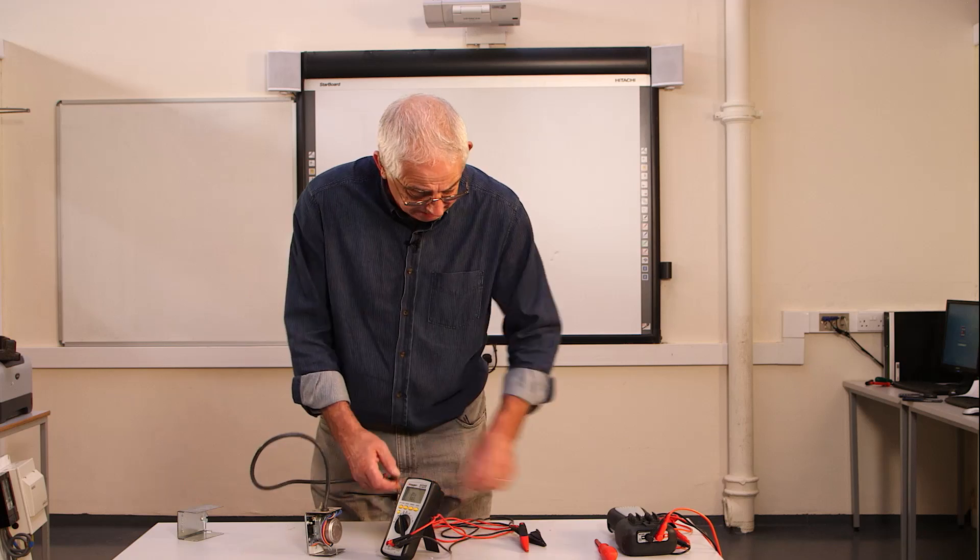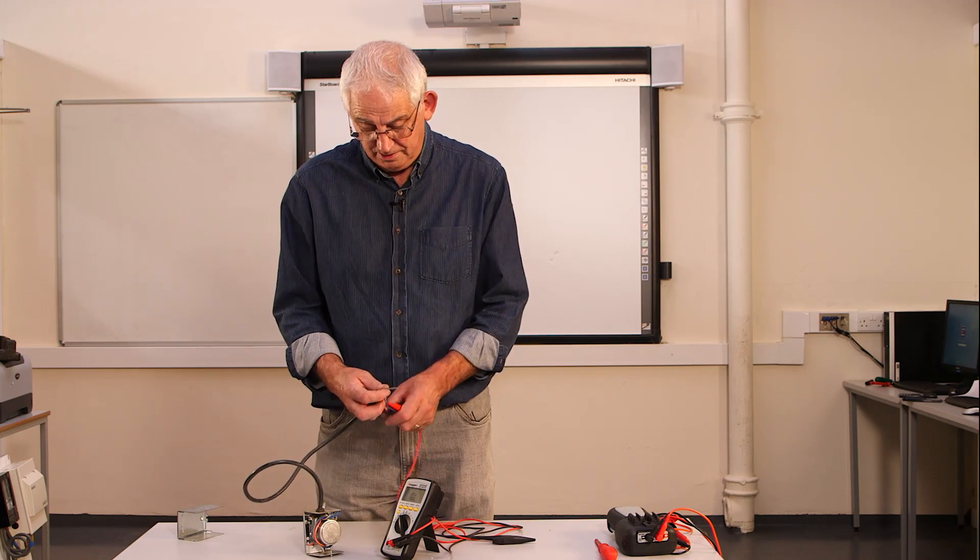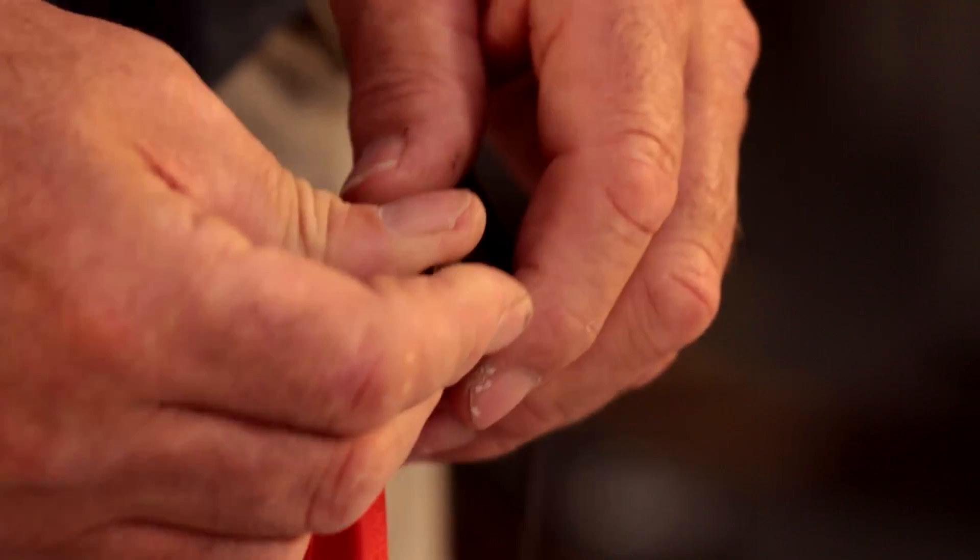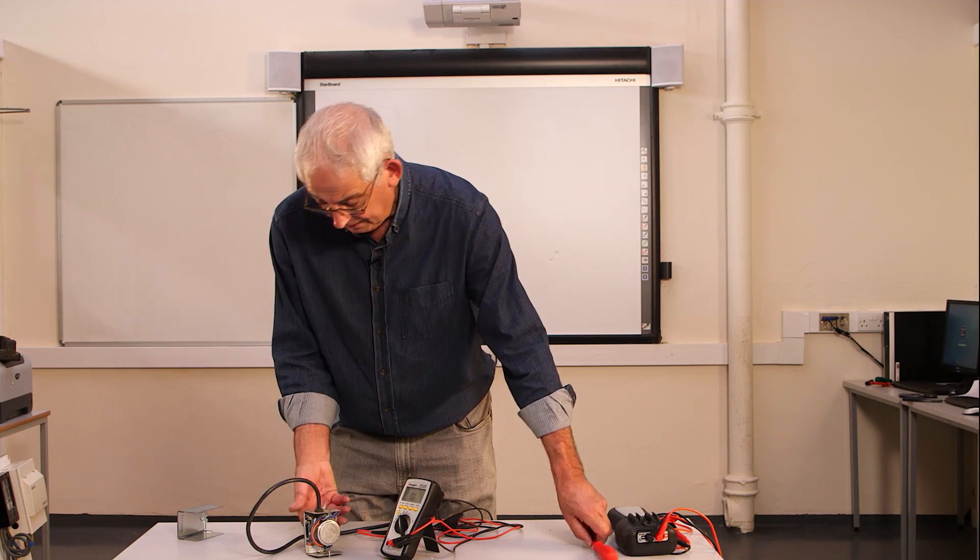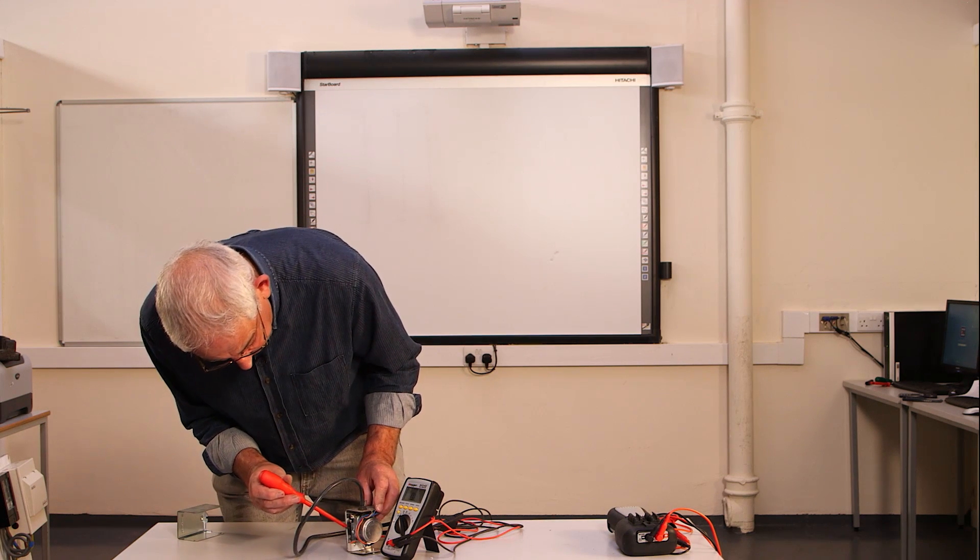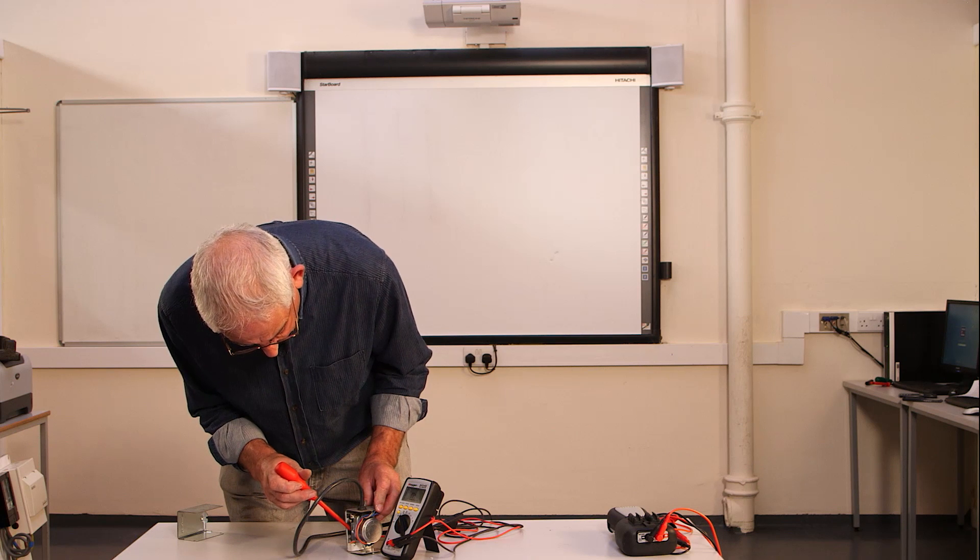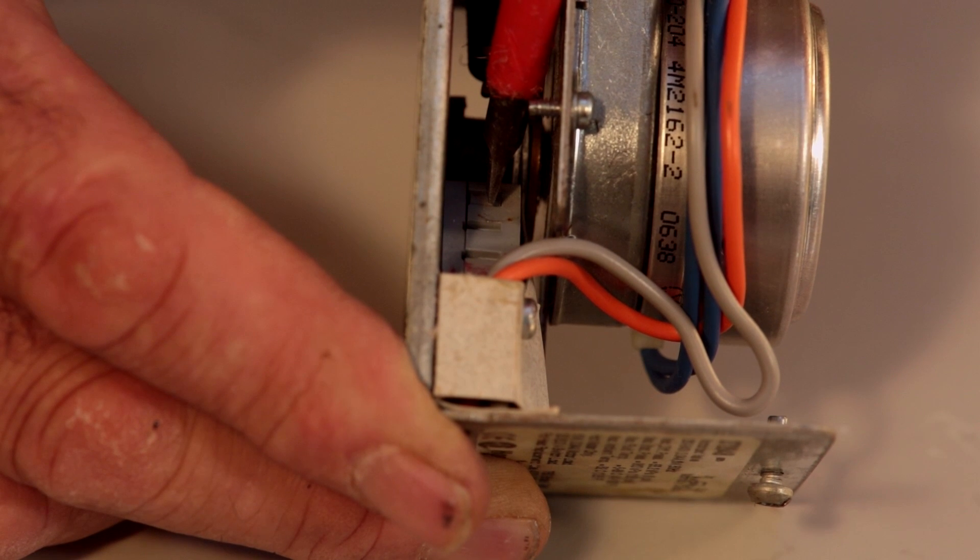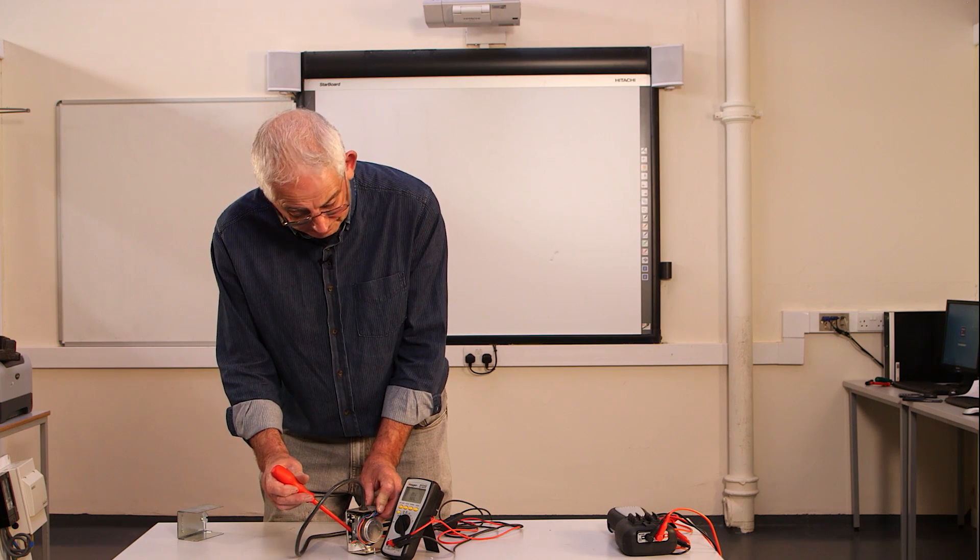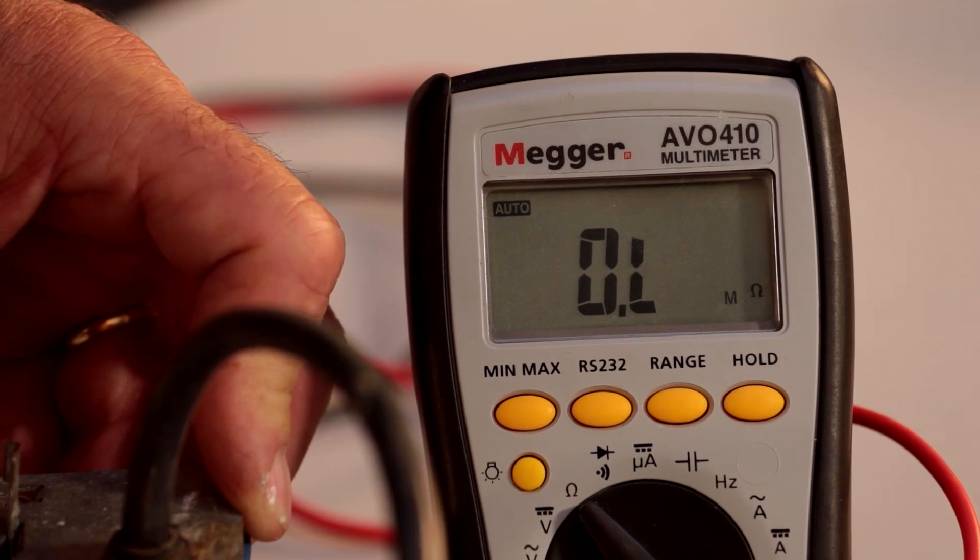We need to connect our multimeter to the grey and the orange and then with the screwdriver just push the micro switch contact down and we should get a reading. So, you can see now by the reading on the micro switch, we've actually got a closed circuit.